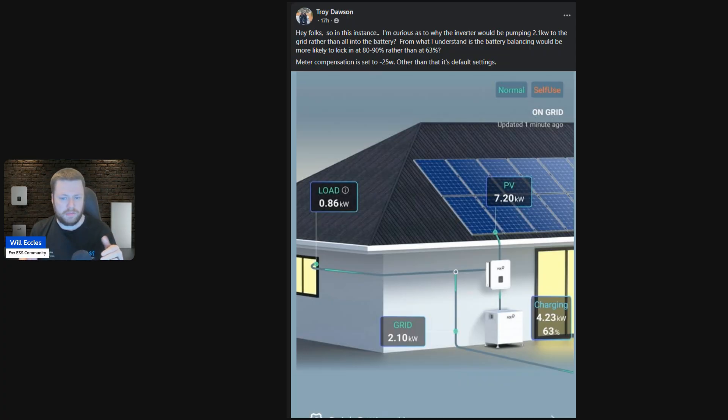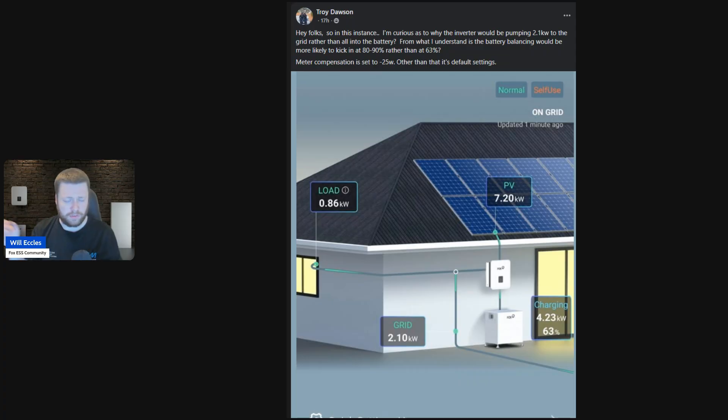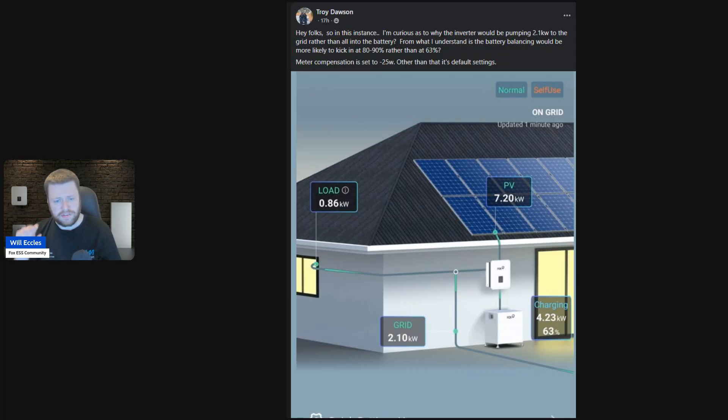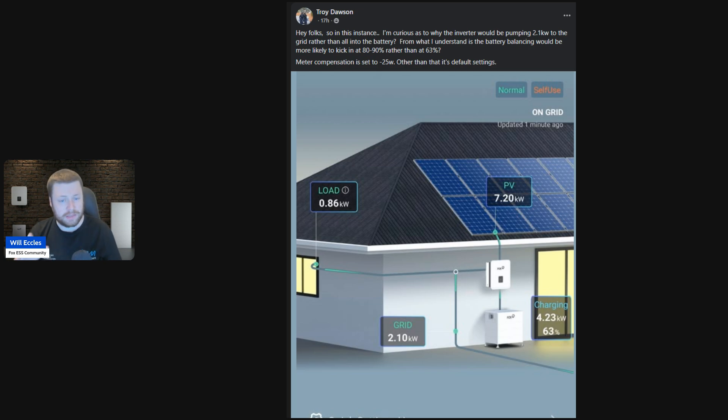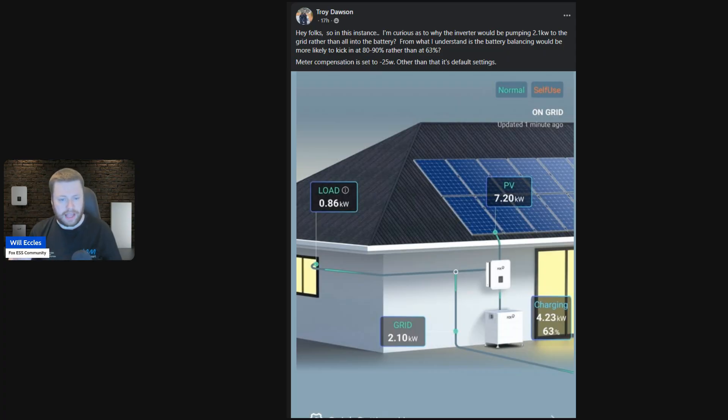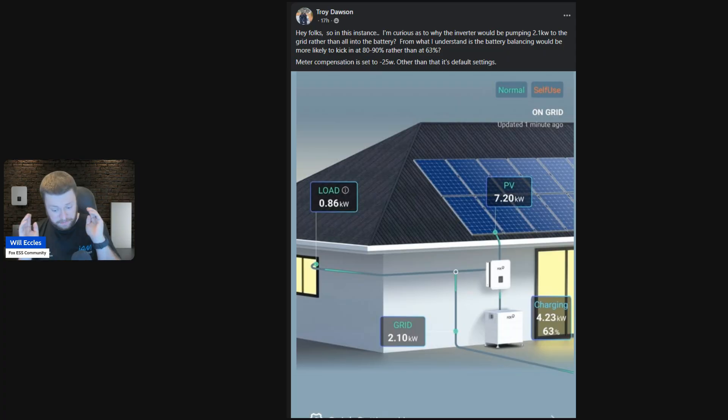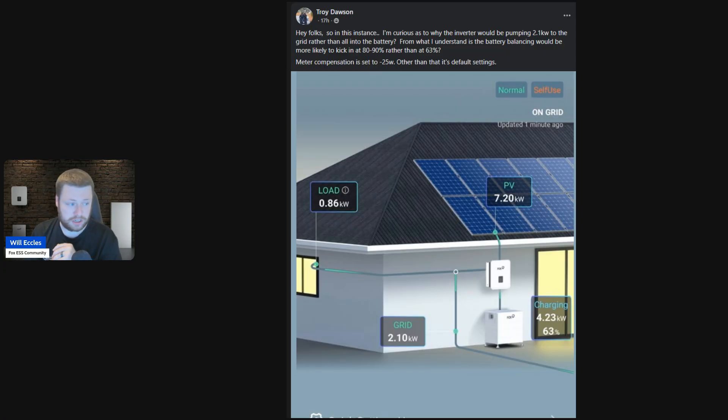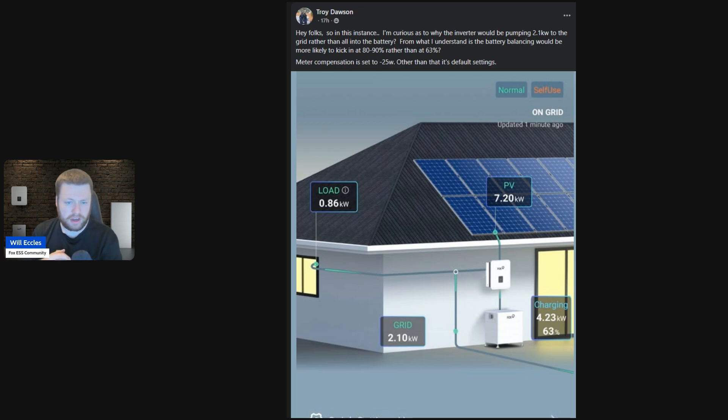So the BMS's job—the battery management system, which is normally integrated into the master battery module but sometimes is separate if you're using some of the older batteries like the Miras or the HV2600s—they have a separate physical BMS. The BMS's job is to safely allow maximum performance, is constantly trying to allow you to charge and discharge optimally and at the maximum that you can do safely, subject to the algorithm around the charge and discharge current. If the BMS is always trying to provide you the most charge and discharge capacity, seeing something like this—charging slower than what the PV is generating—it's probably a good indicator that the battery model, the capacity, the voltage that is, is probably the limiting factor here.